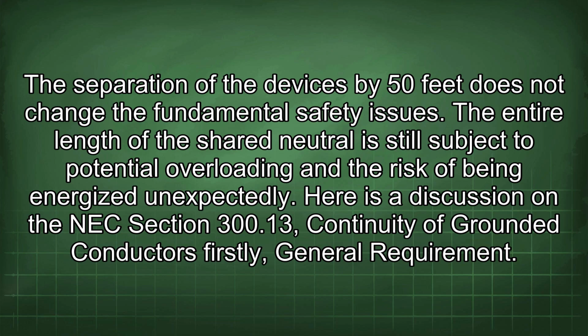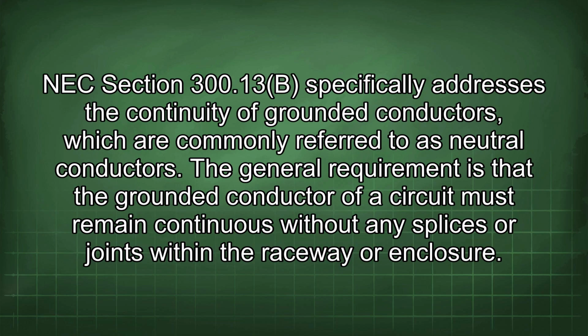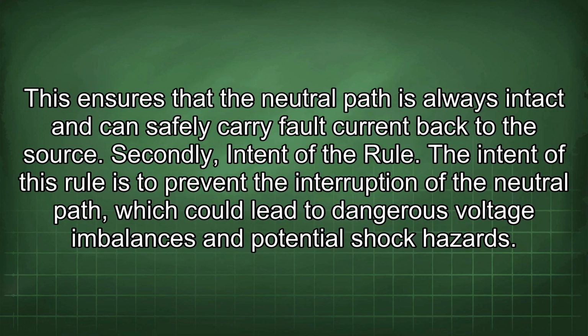Firstly, general requirement. NEC section 300.13b specifically addresses the continuity of grounded conductors, which are commonly referred to as neutral conductors. The general requirement is that the grounded conductor of a circuit must remain continuous without any splices or joints within the raceway or enclosure. This ensures that the neutral path is always intact and can safely carry fault current back to the source.